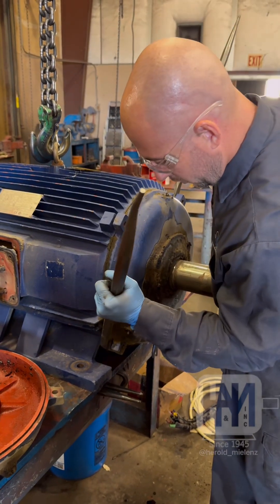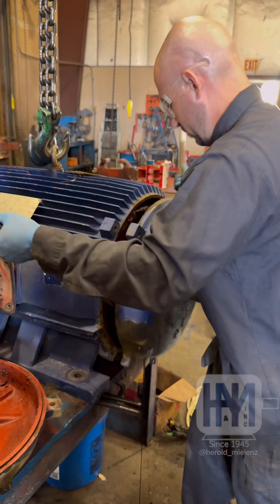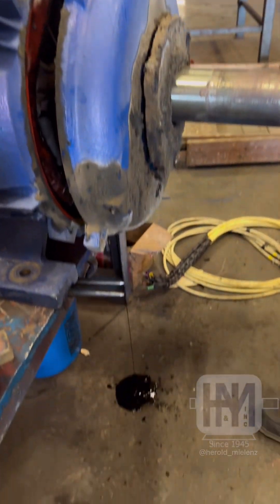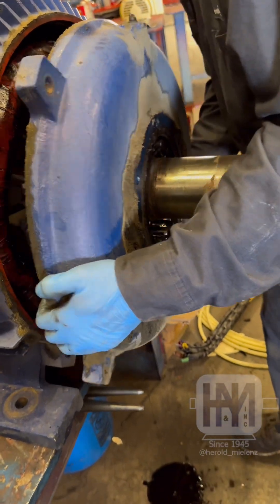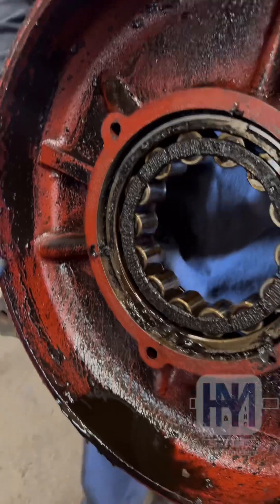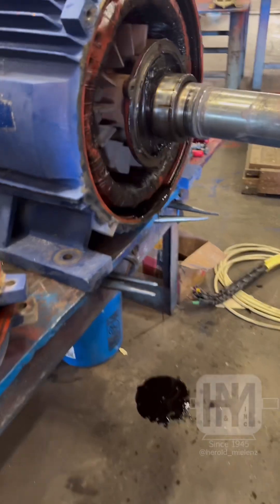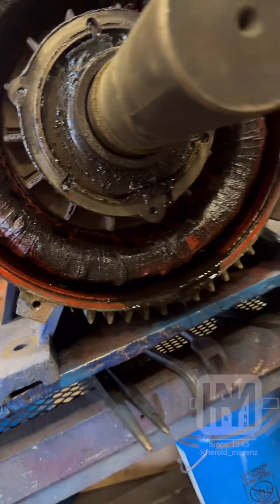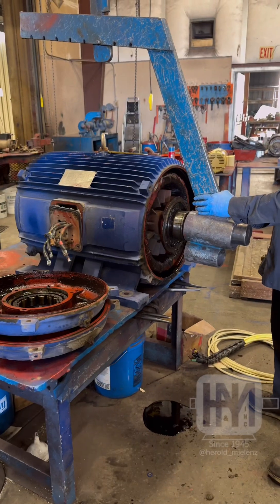Let's see if this will come off nicely for us — if not we'll just have to knock that rotor through. Beautiful. Uh oh — we've sprung a leak. Gotta get some floor sweep. The roller bearing is criminally under-lubed.